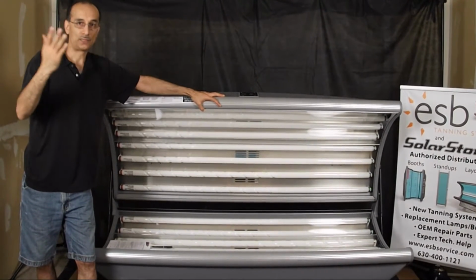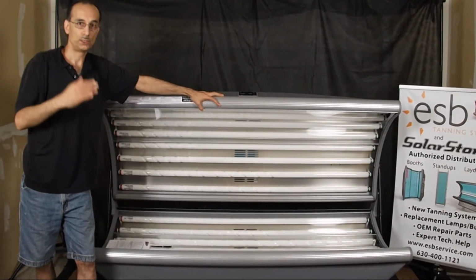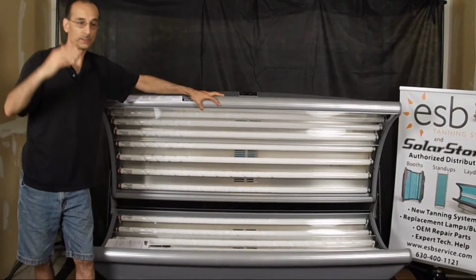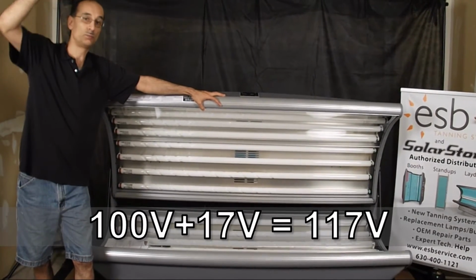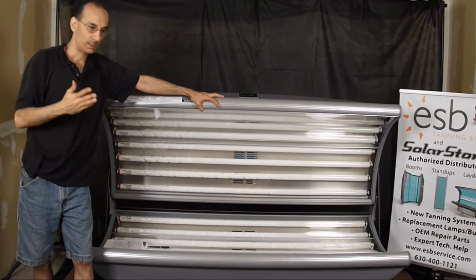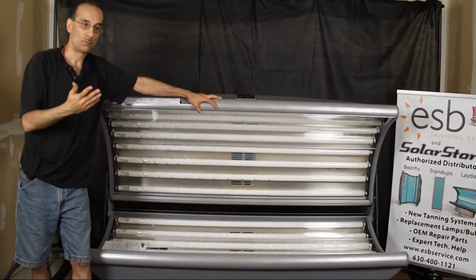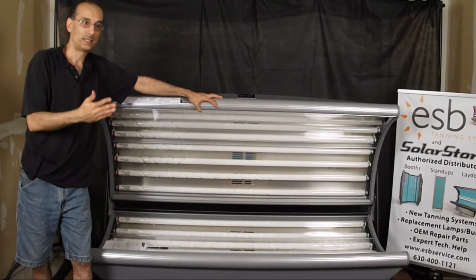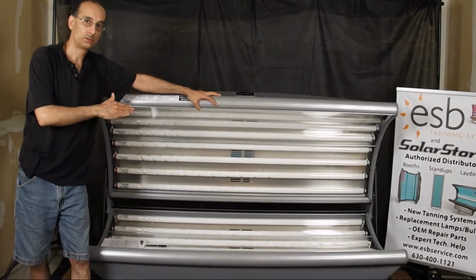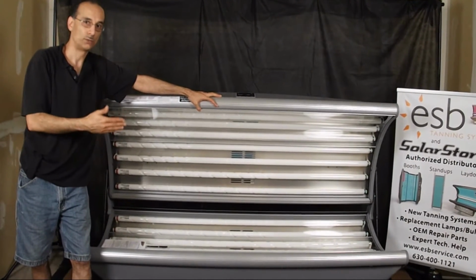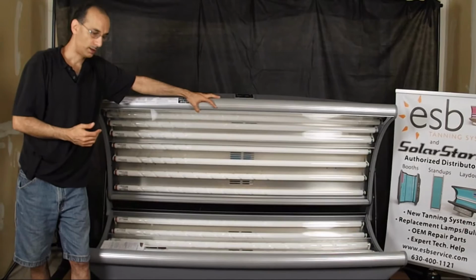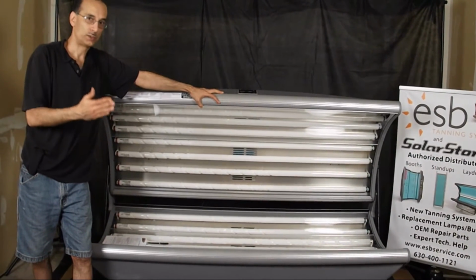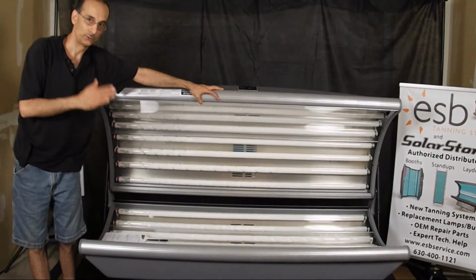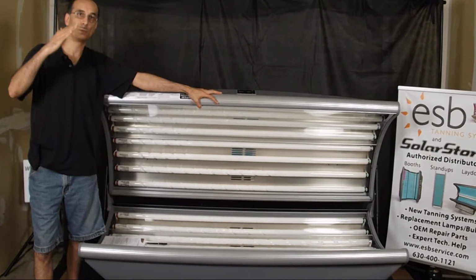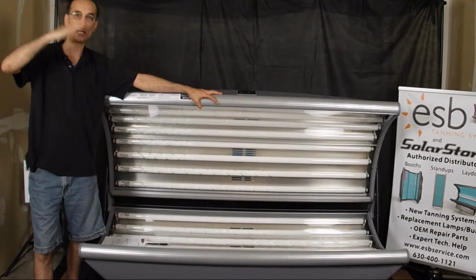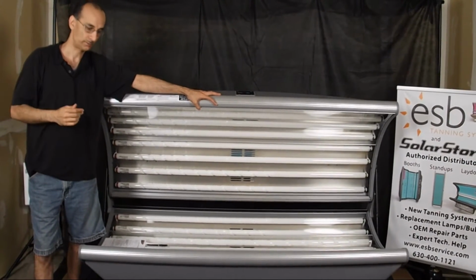If you were 17 volts too low, then you would need, roughly, a boosting transformer. They both start out the same. A buck booster starts out the same. It's either turned into a bucker or a booster, depending on how it's wired up. But that is what determines if you need the transformer. Basically, if your receptacle voltage is too far outside of that specified range.